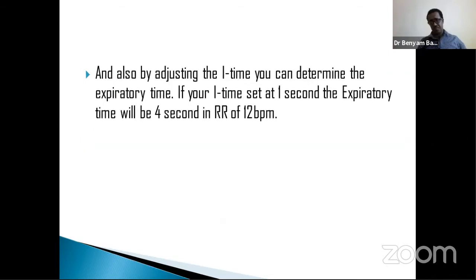And also, in this time, we could also adjust the inspiratory time, yeah? So adjusting I time can determine the expiratory time, because if you adjust I time for a respiratory rate of 12, the patient will have a breath every 5 seconds, yeah?